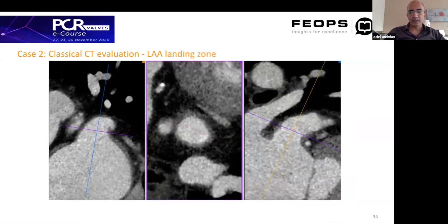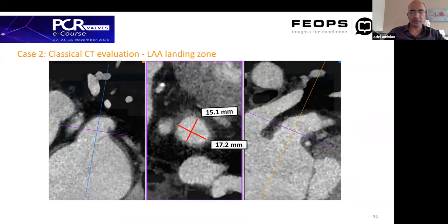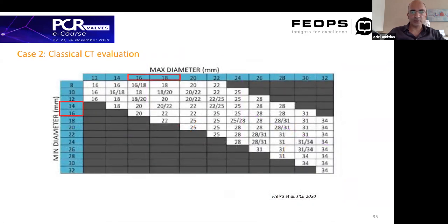So looking now at the landing zone, we see that it's relatively small and not so eccentric. We have a minimum diameter of 15.1 millimeter and maximum of 17.2 millimeter. So the mean diameter is around 16. Looking again at this very nice sizing chart from Dr. Frexa, we see that the minimum is between 14 and 16, the max between 16 and 18. So we have to go for a 20 or a 22 millimeter device.